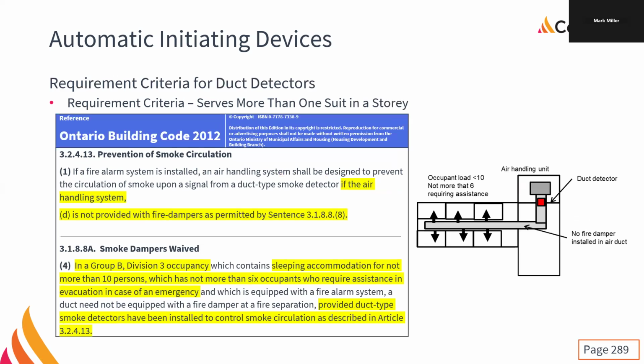And then if we have no fire dampers, usually we have fire dampers built in, right? Nothing to do with us. The sheet metal mechanics are installing them as needed, but in small buildings, we might not be required to have them. Then, if there is no fire dampers provided, then we have to put in the duct detector. And this is what we see in small residential.